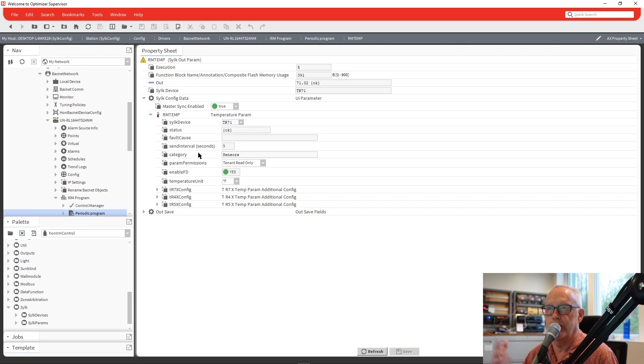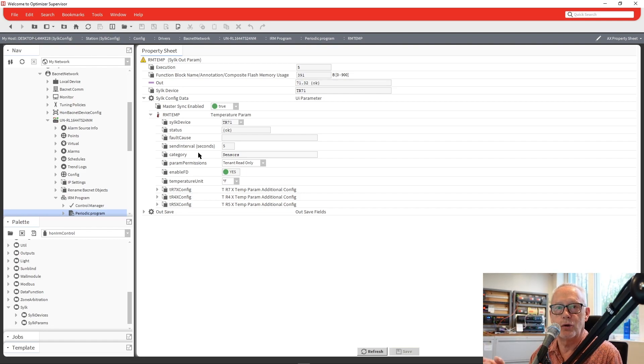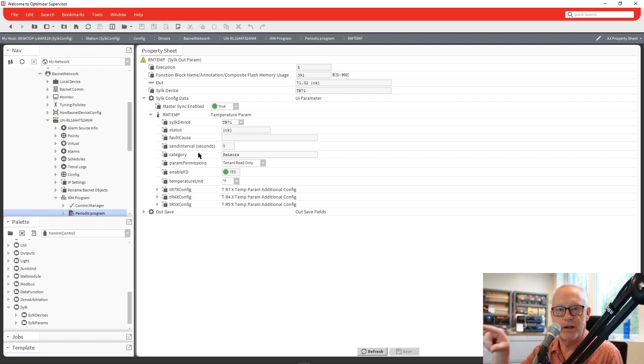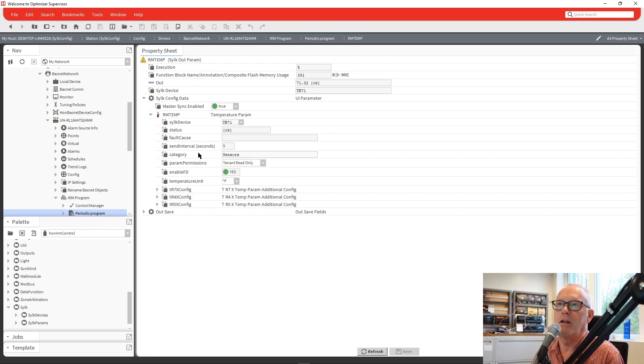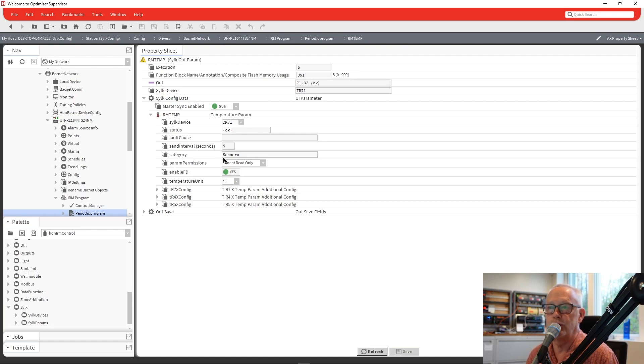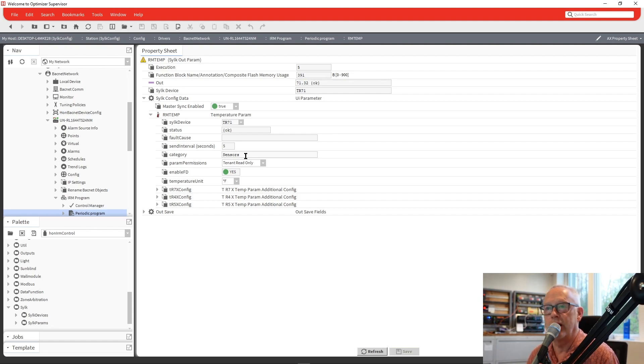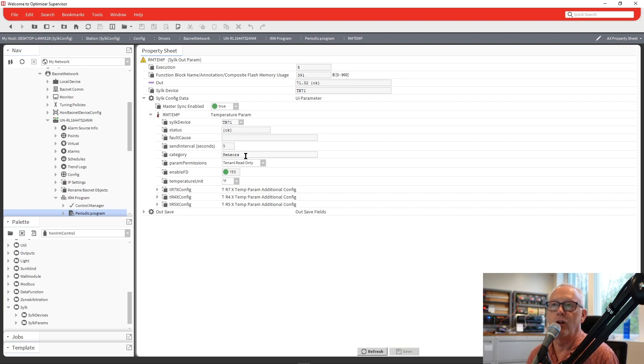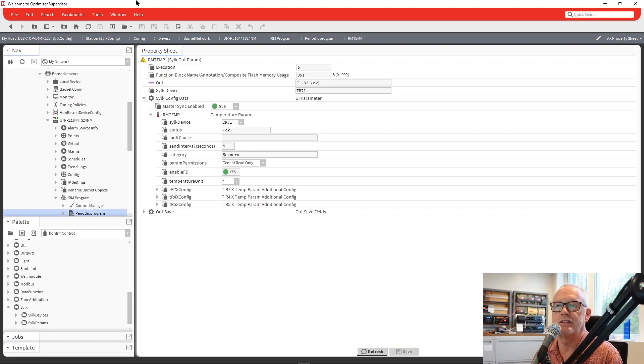And in the TR71, as it was in the Spyder Classics, you had categories so that when you were in contractor mode, you could go to different categories, sensors, set points, statuses, whatever, and group your points that way. We have the same ability to do that here in the IRM tool. So when you add a parameter and you choose a name for a category, it automatically creates that category within the actual Sylk device. So if we add another point for set points, which we're going to do, we call it set point. That will get added. And then if we add other points and use the same category name, those points will be grouped together so that you can see them from the device itself.